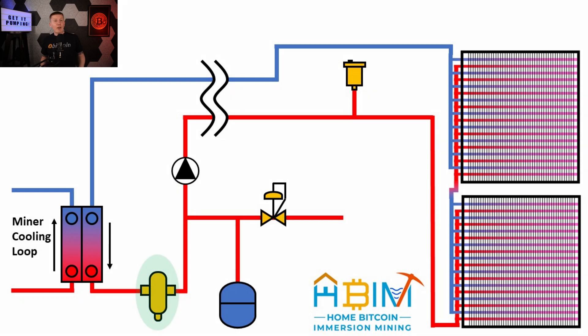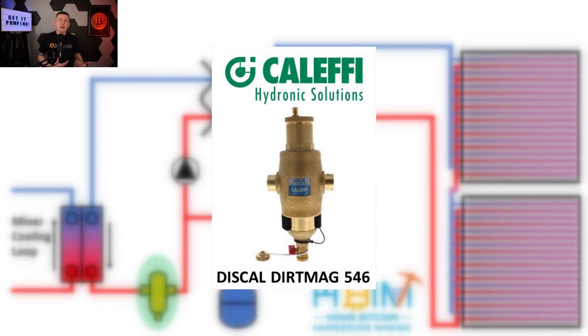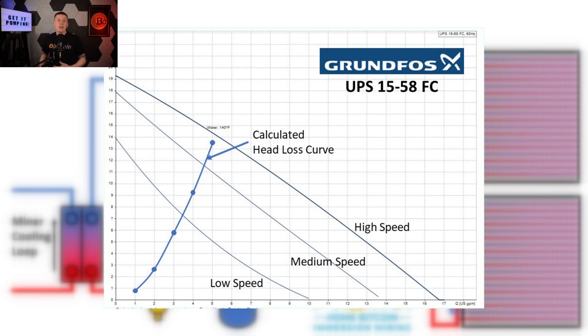Next up is the air and dirt separator. You can buy dirt separators and air separators as separate components, but Caleffi makes a combined air and dirt separator — the model I chose is called the Discal Dirtmag 546. Next up is the circulator pump. In the last episode I covered how to calculate an overall equivalent length and combine that with fluid flow rate to size the pump using pump curve charts. The result is my system head loss curve overlaid on the pump curve chart for my chosen pump, the Grundfos model UPS 15-58 FC. I chose a multi-speed pump so if I messed up my math, I have options to increase pump speed and still make the system work.